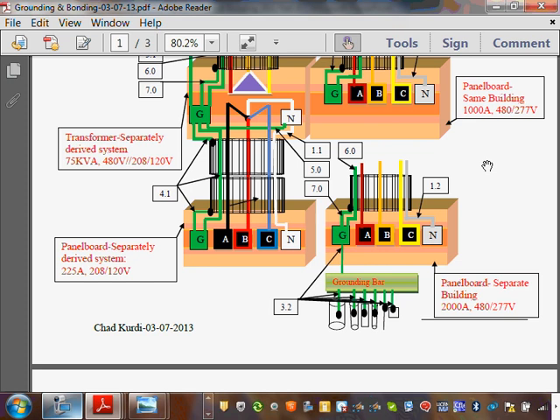Yes, sir. Does the separate building ground go to the service equipment panel board's grounding bar, or is it tied in the service equipment panel board? Good point. You're talking about this. Where's that ground go? Okay, good point. Now remember, these are completely separate buildings. Then at the second building, you are to create a new grounding electrode system right in here, meaning you have to tie to the steel, all the grounding electrode system. You need at least one here, right? Exactly like a service. You need a concrete encased electrode or steel. But if others exist like water, you have to tie to them. So you have to create a grounding electrode system exactly like at the service, 3.2 I call it, with a full-size equipment grounding conductor all the way to the panel, one or multiple. You can bring some of these here too, exactly like we do at the service.